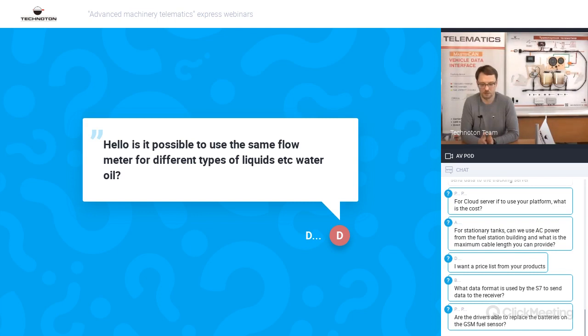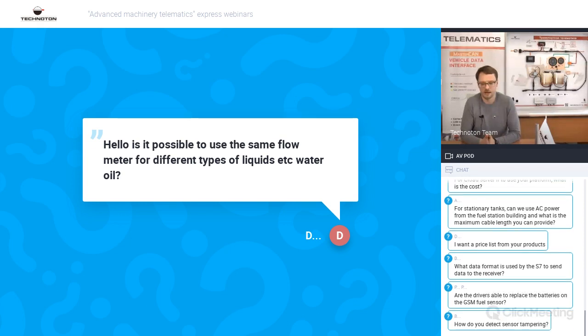But as for now, it's not recommended to use a flow meter for water. You can use it for fuel, for oil, like heating oil, but not for water, because water has different properties, and the flow meter will not work for a long time - the wear out will be too quick. So the flow meter is used for fuel and fuel-like liquids, like heating oil, marine oil, all that kind of liquids.